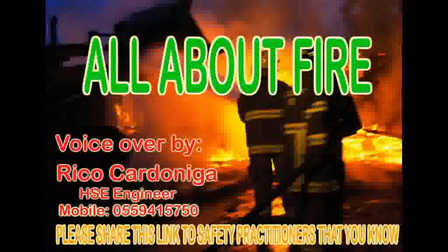Identify the types of fire and fire extinguishers. Class A, fires which involve solid materials such as wood, paper, cardboard, textiles, furniture, and plastics where there are normally glowing embers during the combustion. Such fires are extinguished by cooling, which is achieved using water.